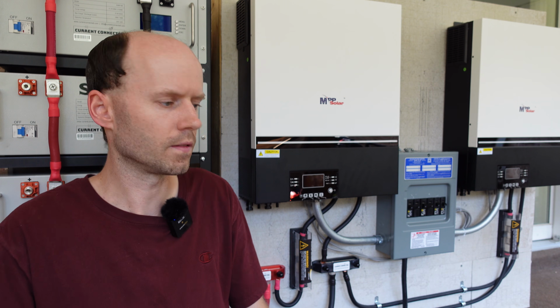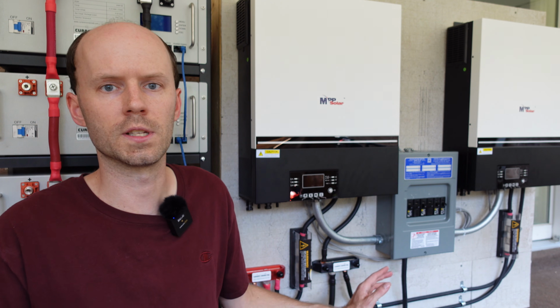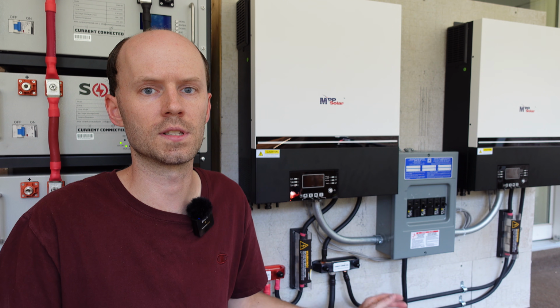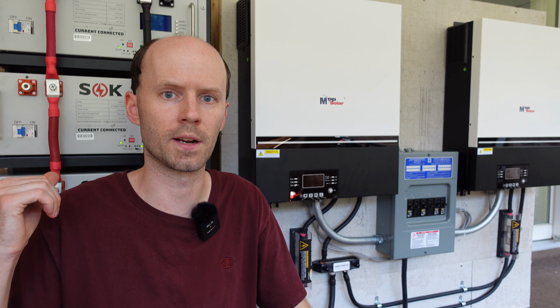Additionally, fusing. Ideally, there would be a fuse coming in before these bus bars. You saw I put 2 fuses after the bus bars. And those fuses after the bus bars are to protect the cabling, the 1/0 cable from overcurrent. Ideally, there would also be a large fuse on the 4/0 cable to protect that. However, I feel in this particular setup that is sufficiently protected between those 2 fuses I installed and the 4 circuit breakers on each battery. If I were to wire any more batteries, I probably would use a fuse on those 2 conductors.